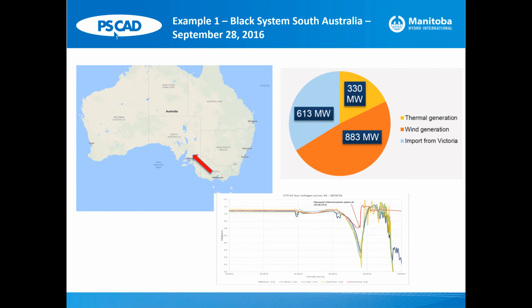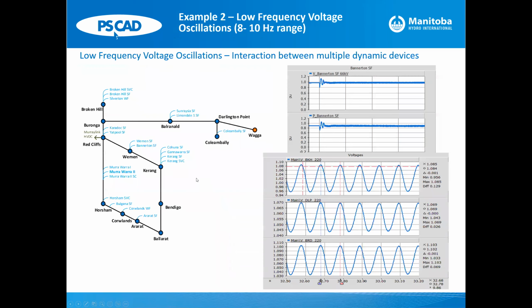And in this case, what we found is there was a particular oscillation that was seen in the system. So these type of frequencies that you can see, only a part of the system was initially modeled in EMT. And then it was found that actually you need to go further out and model Queensland and South Australia. It was only when we had to model the whole territory that it was possible to capture these type of behaviors in electromagnetic transient tools. So the need for modeling wide area systems became of paramount importance, because if you just take a small region of the system, it may not capture the transients that you are looking to study. I'll give you one example.